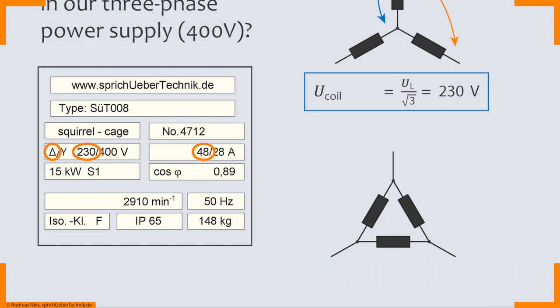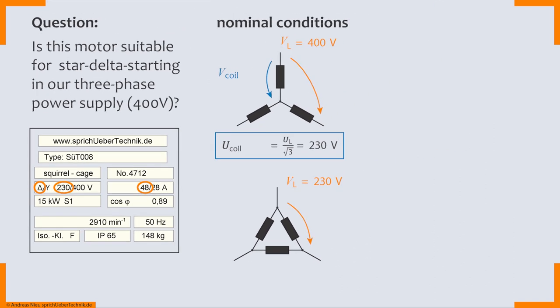For delta connection we need to use the first value respectively. Hence with the delta connection the nominal phase-to-phase voltage is 230 volts. I also put that there for you and now again the question what does this mean for the coil voltage. Well that's actually very easy. At each coil there's going to be the phase-to-phase voltage. So coil voltage equals phase-to-phase voltage equals 230 volts.